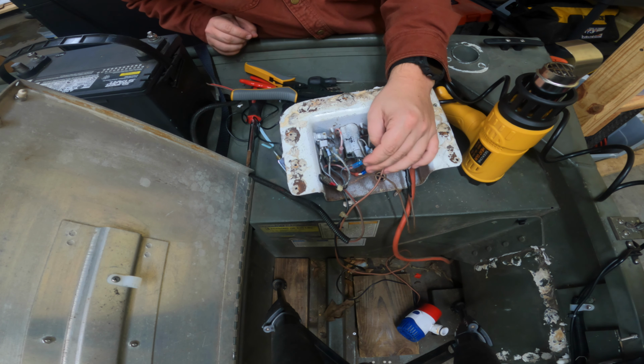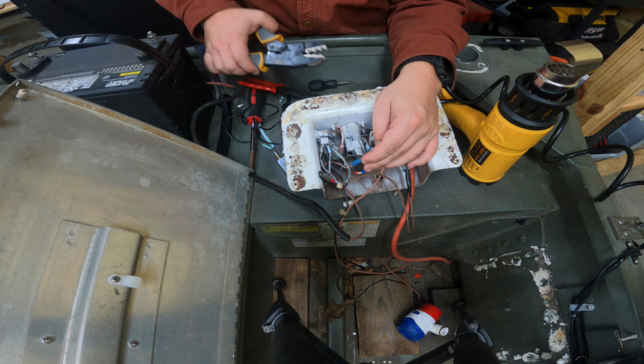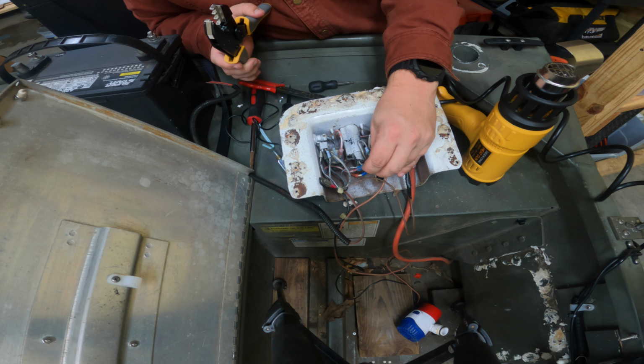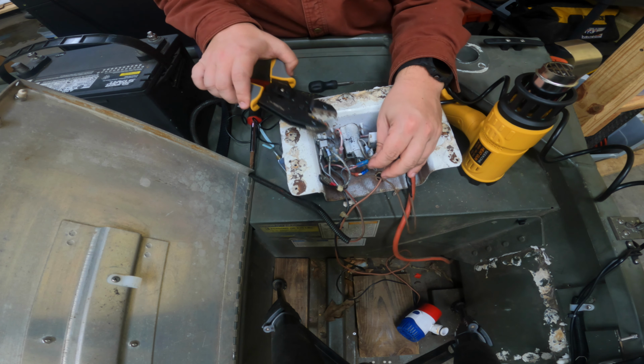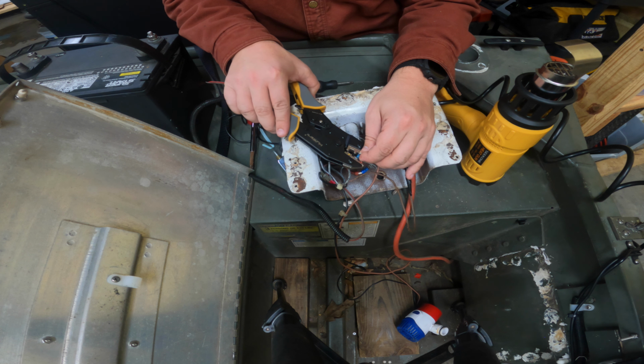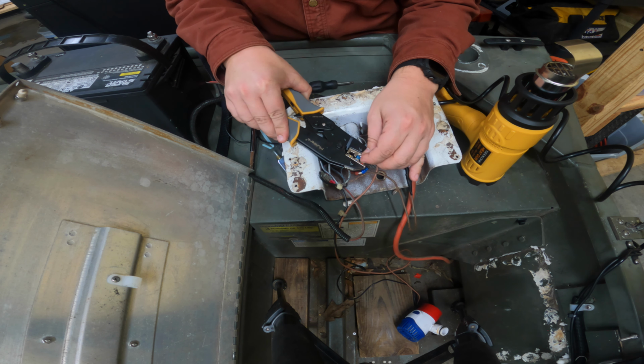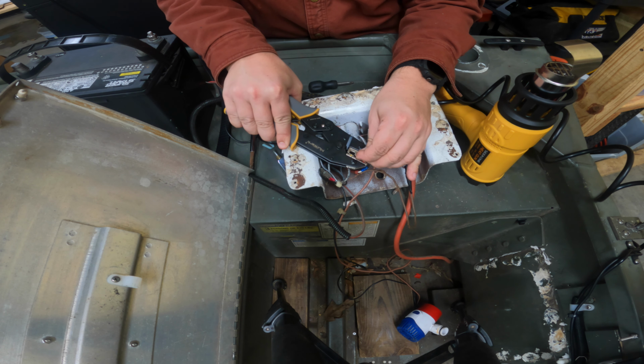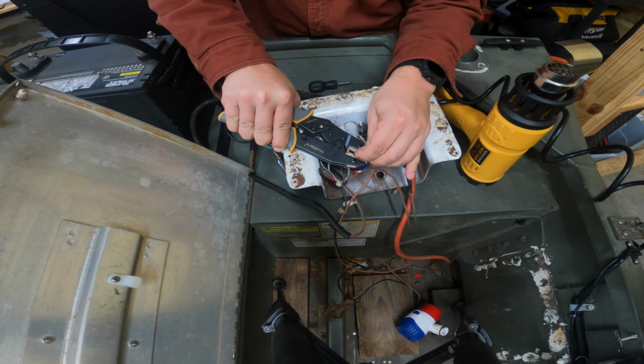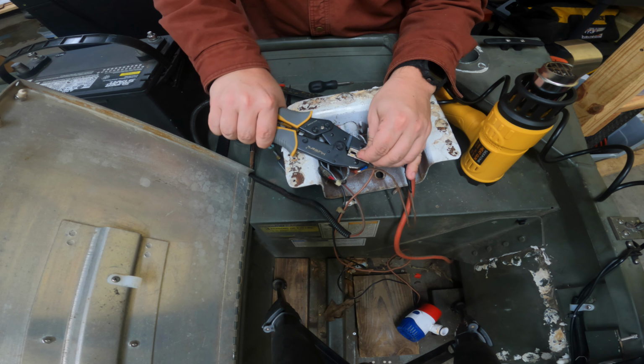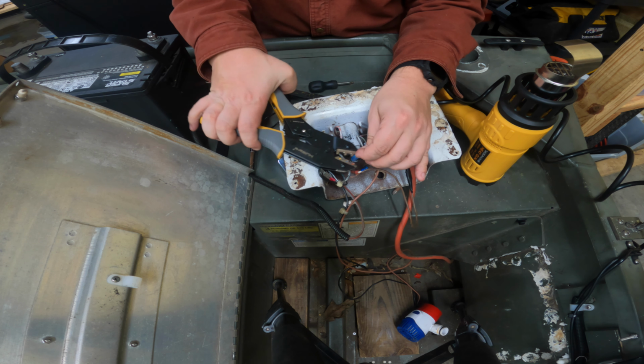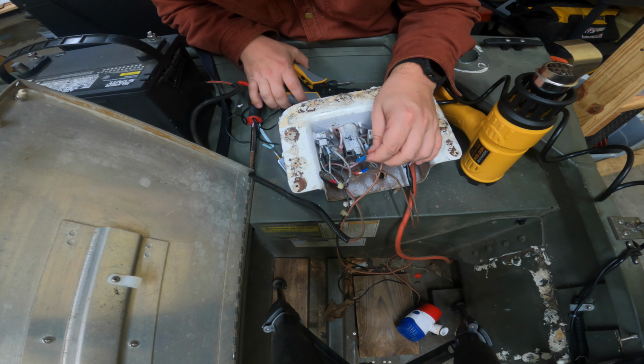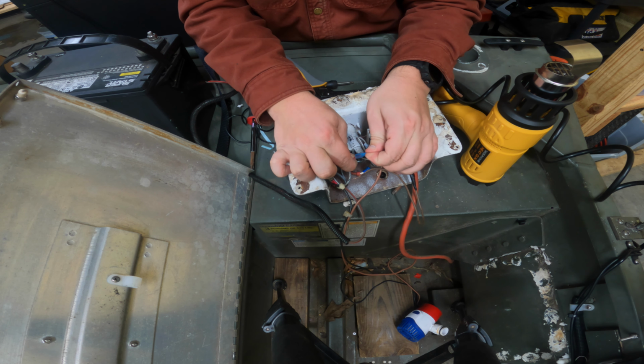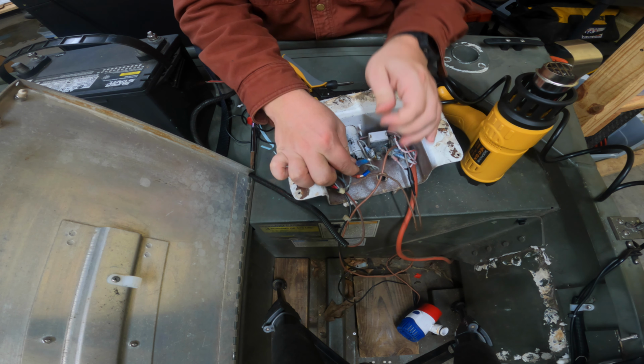Looking at it a little bit closer, this is actually closer to 16 to 14 gauge. We got our crimping tool, we just slid this down on that bare wire, making our best to make sure we don't get insulation in there. Put our crimping tool on, and we're just going to crimp that down. And that should be good and crimped. Do a pull test, and that's in place.